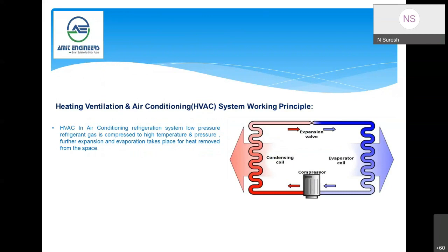So here, this is the basic system. You can see at the center middle, this is the compressor, which compresses the gas, that is the refrigerant, from low pressure to high pressure. Whenever any gas is compressed, it will generate heat. So to remove that heat, there is a condensation process. Here, this is the heat exchanger. In this, we are using a fin tubed air-cooled heat exchanger. The heat is removed here.